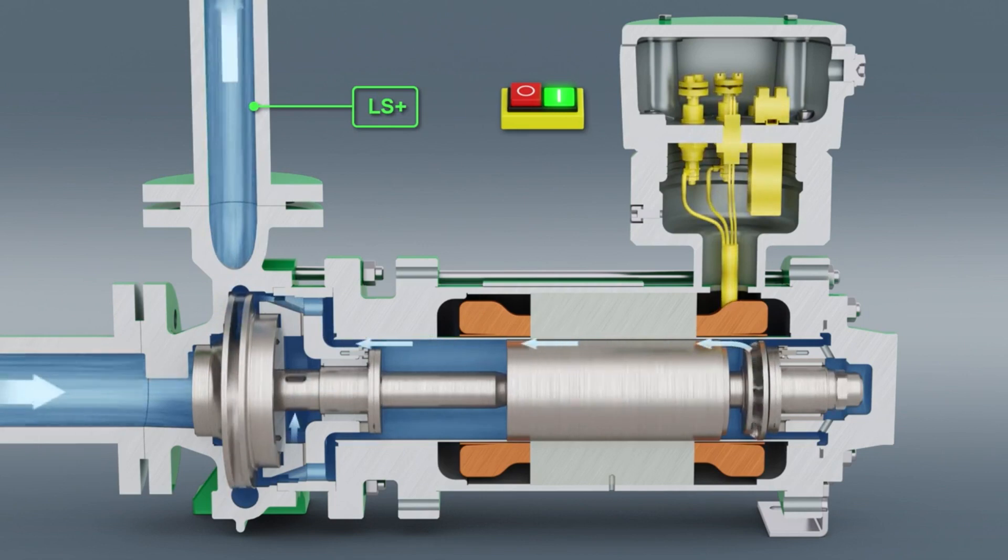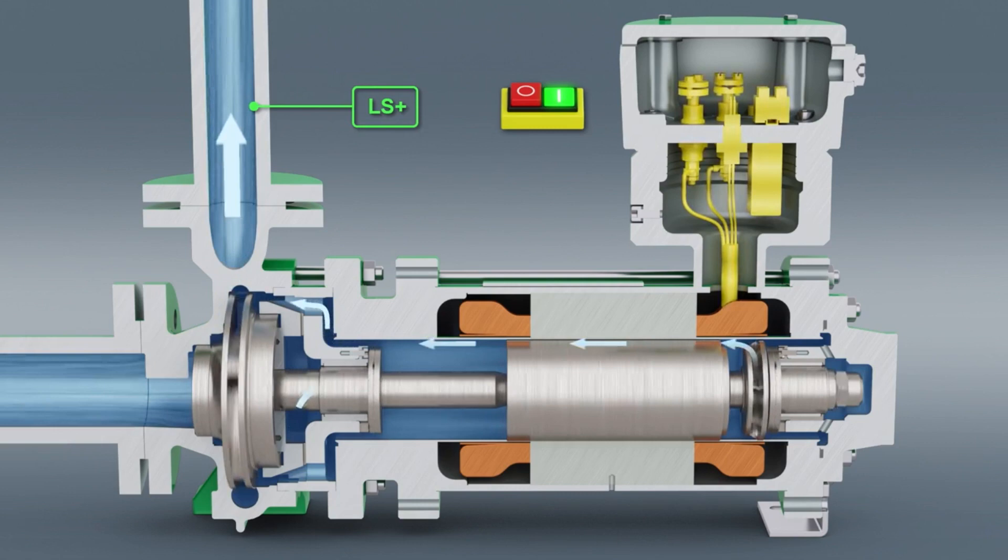The auxiliary impeller is used to overcome pressure loss and enables pumping liquefied gases with an extremely steep vapour pressure curve.